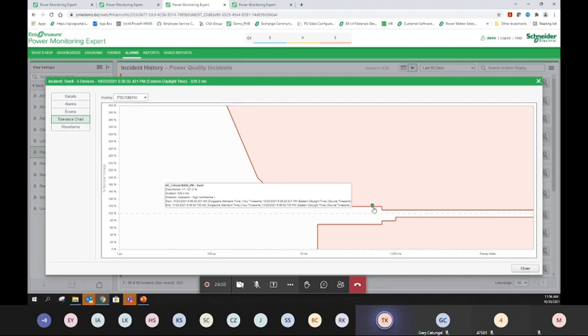If you ask me, if you are in the boundary, you should be looking at your load carefully - what impacts are happening, whether it has affected your MRI machine or one of the X-ray machines, because it's already in the non-tolerance zone. You don't need to be too much of an expert in the electrical area - the software actually calculates it for you.